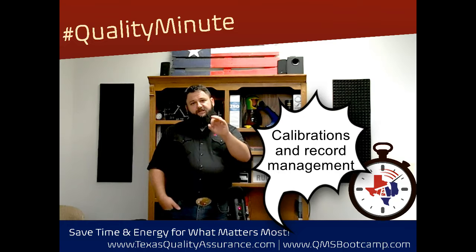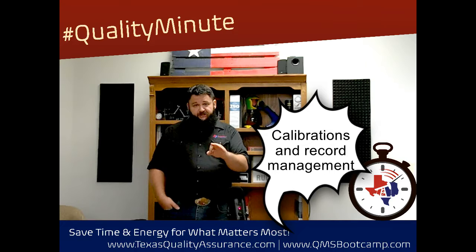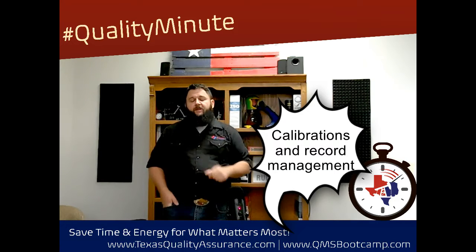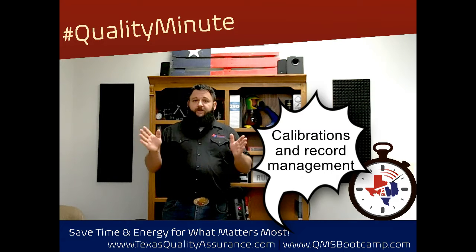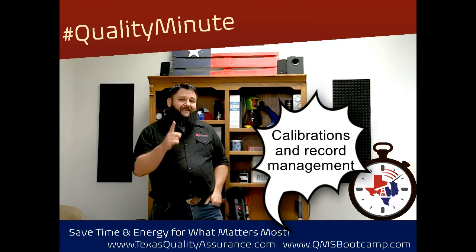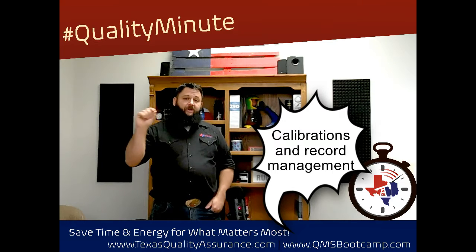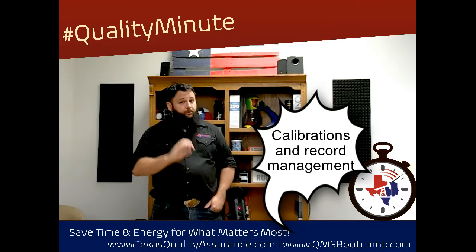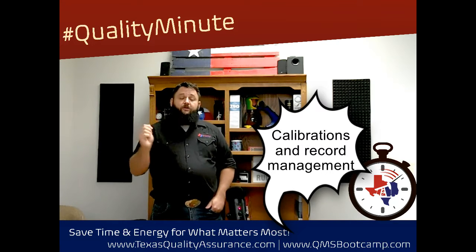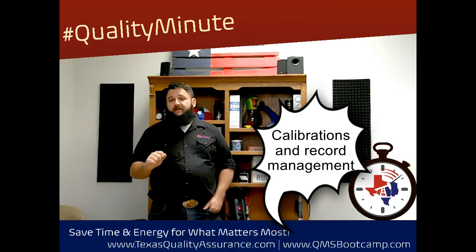Then what you need to do is write a procedure. This procedure needs to be signed off by top management and in your operations management and leadership team, so that everyone is for sure on board. So what we're going to do is train, once we get that procedure written, it's going to define a few requirements for us. One of those requirements is a daily spot check. What this means is that anyone on your team who is performing a documented inspection, any inspection where we write down the numbers or make a go, no go decision based off of it, they need to perform a spot check of their equipment that day before they use it on anything that they're measuring.